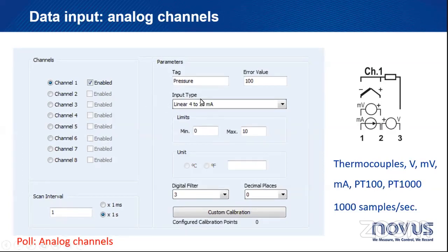You will see a linear 4 to 20 milliamps pressure transmitter connected here. So in that case, you can select your error value and you also have to select the limits. So what does that mean? Well, that means I want to go from 0 to 10: when the input is 4 milliamps, the value is 0. When the input is 20 milliamps, the value is 10. You choose the number of decimal places and you can also write down here your unit. So I could type down here bar or millimeters of mercury, millimeters of water, or inches of water, whatever you want to use here, okay?